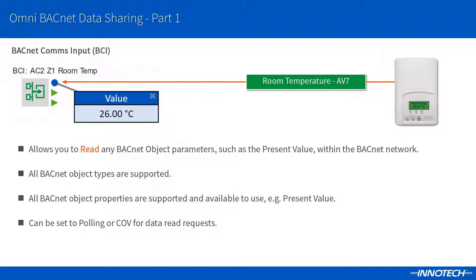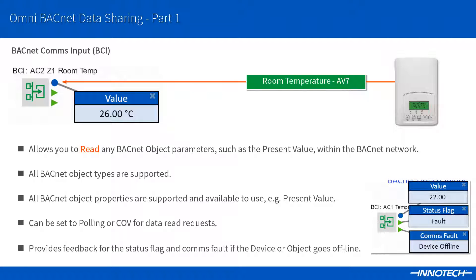The read request can be set to either polling, which asks for the value at specific time intervals in seconds, or change of value referred to as COV, which can offer a more efficient method of value update and can reduce network traffic. The block also provides feedback in relation to the status flags and comms fault if the device or object being read goes into fault or is offline. In this example, the default value configured in the block's properties is shown as the device has gone offline.